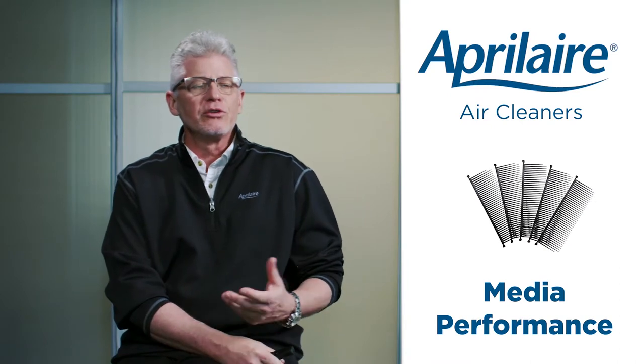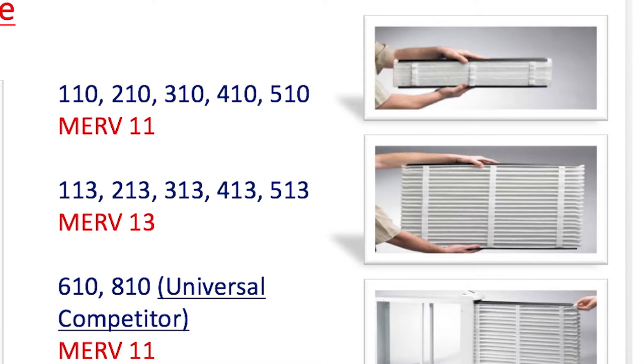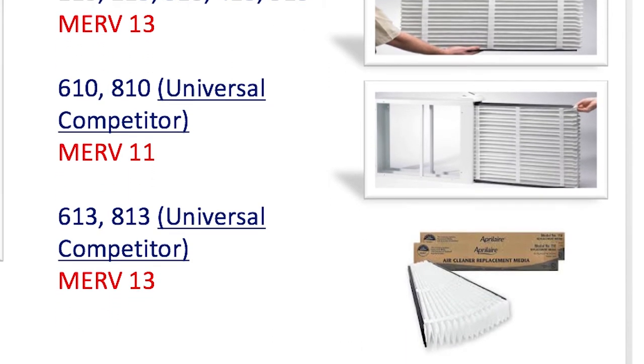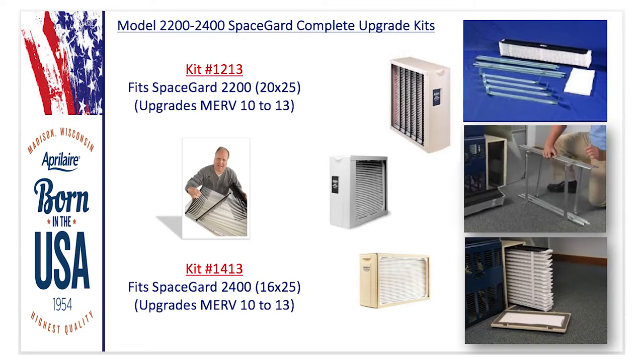Let's talk about media performance. Many of you remember the old Aprilaire SpaceGards with the combs and pleat spacers — that has changed. All our filters now have model numbers ending in 10 for MERV 11 and 13 for MERV 13 — for example, 110, 210, 310, 410, 510. We also have upgrade kits for the old SpaceGard 2200 and 2400 cabinets: the 1213 kit for the 2200 and the 1413 kit for the 2400, upgrading them from MERV 10 to MERV 13.